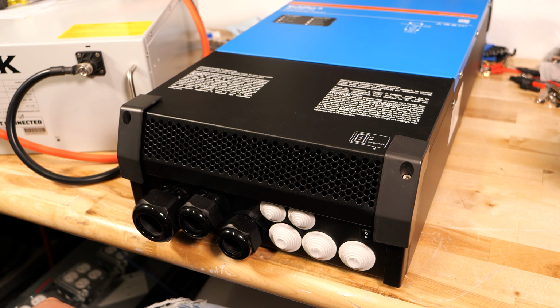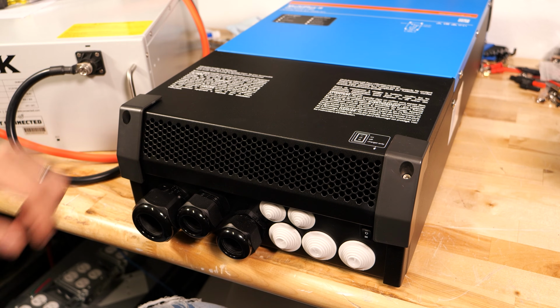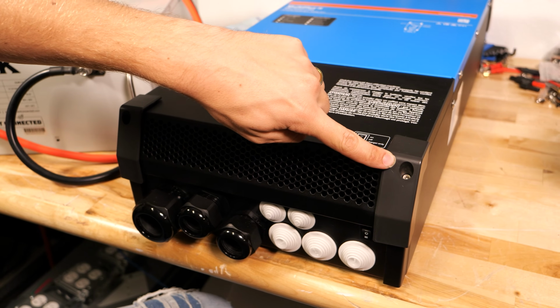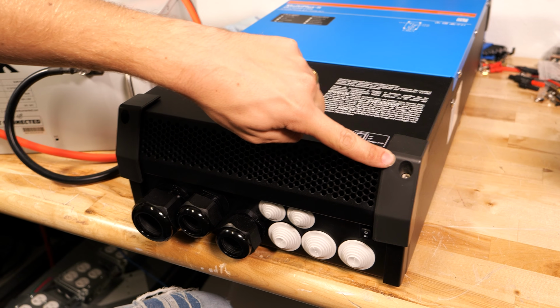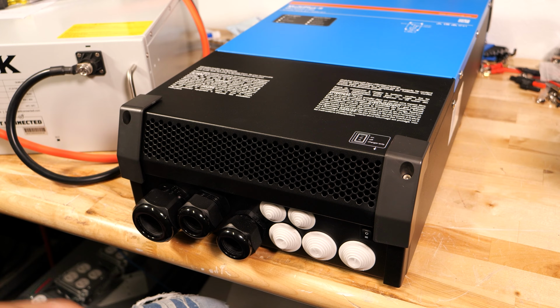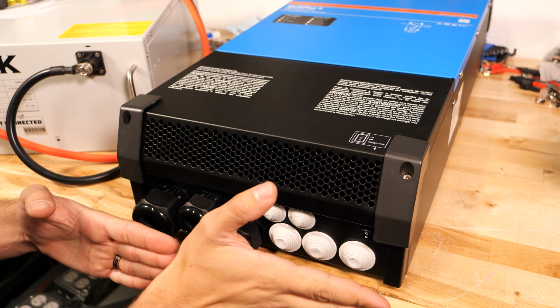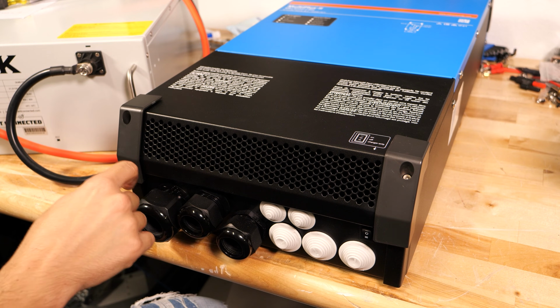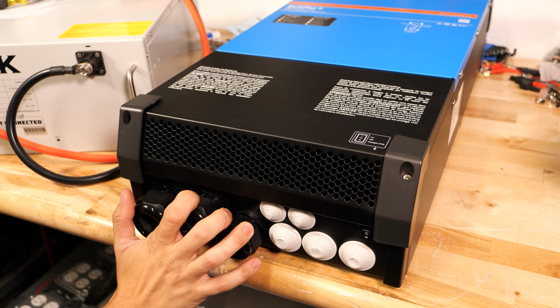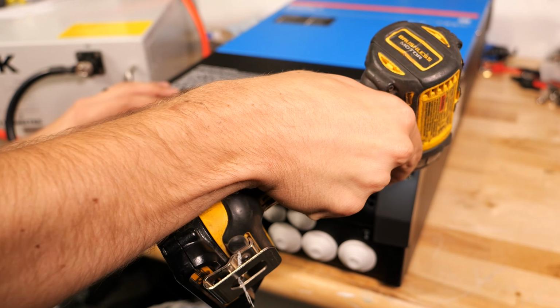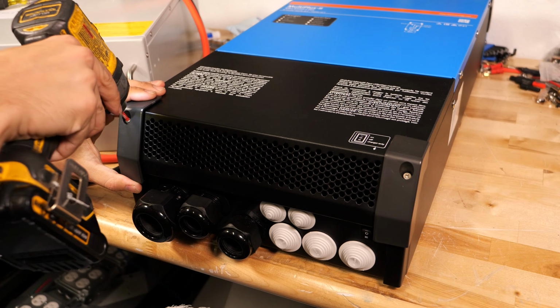It's perfect. Now, one of my complaints in the past on Victron MultiPlus inverters is that there's two screws on the bottom of the compartment. And with this one, they've moved them. You can see they're up here on this upper corner instead. That's really nice in the event you put this close to a floor and use, say, Seal-Tight 90 connectors to bring your electrical connections out of here. Now you can actually take the screws out without being at a really awkward angle.